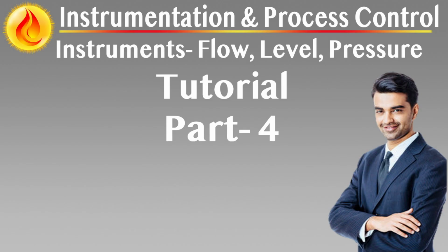High accuracy, high repeatability, but service dependent. Turbine meters offer accuracy better than ±0.5%, with some calibrated units reaching ±0.15%. Excellent short-term repeatability, crucial for batching and proportional blending. Fast response time, ideal for dynamic flow conditions. However, their performance depends on stable fluid viscosity and temperature, clean, non-fouling fluids free from solids, wax, or entrained gas, stable upstream flow profile to ensure even rotor loading. Common applications: LPG, gasoline, jet fuel, diesel, and light oils; natural gas, nitrogen, and compressed air with proper bearing and material selection; hydraulic fluids, demineralized water, and solvents in industrial metering skids.